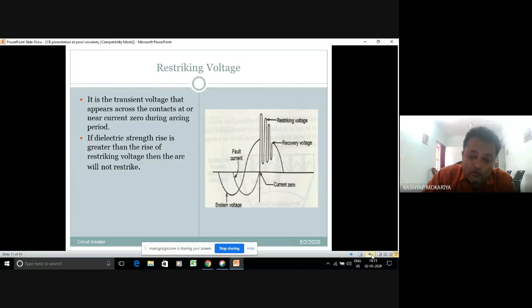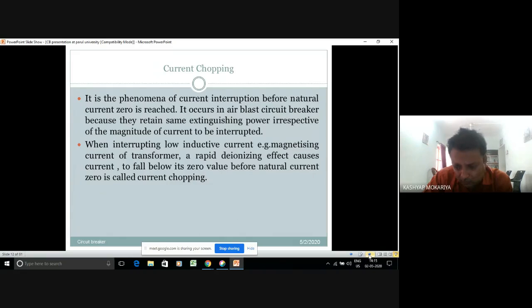But in between, you have to perform those methods, whether it is a high resistance interruption or a low resistance interruption, according to whether it is an AC or a DC breaker. One thing that is asked in interviews in industries when you apply, and in some final year examinations also, is: what is current chopping? It is a phenomenon of current interruption before the natural current zero. It occurs in air blast circuit breakers, and you will find it in some VCBs also, because they retain extinguishing power irrespective of the magnitude of current to be interrupted.